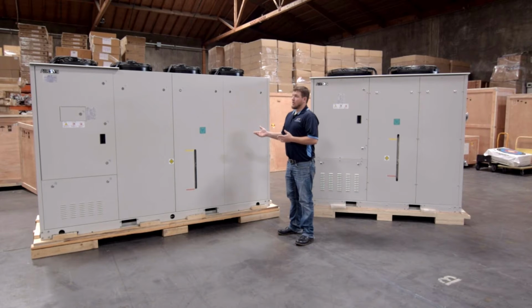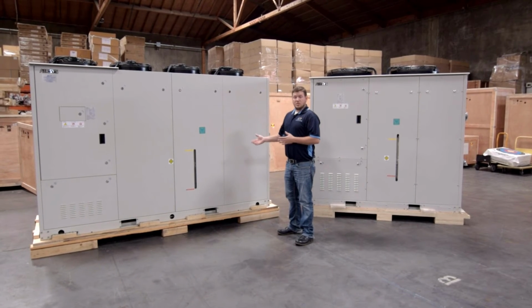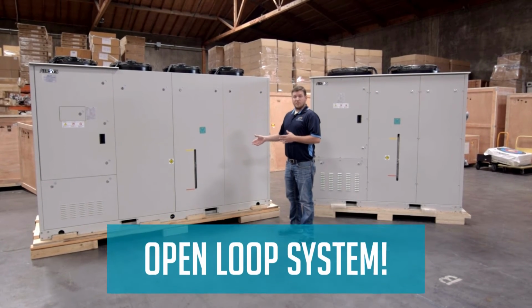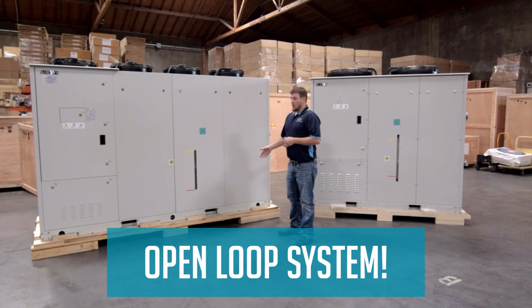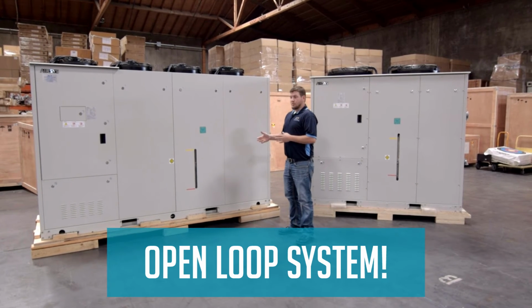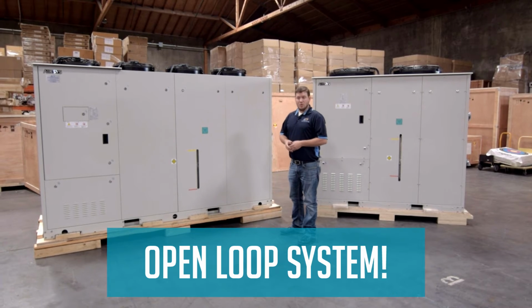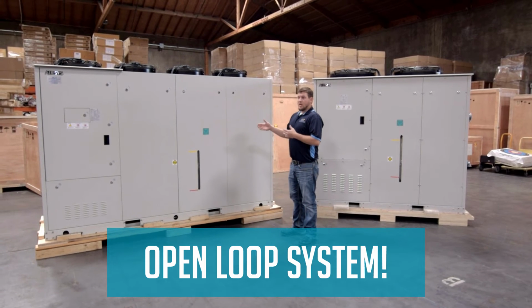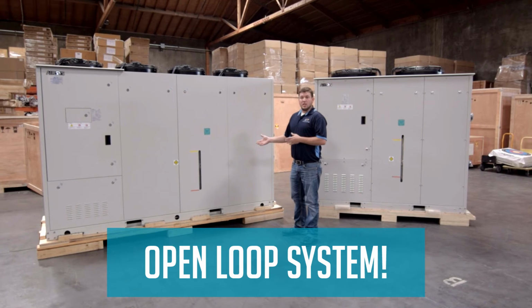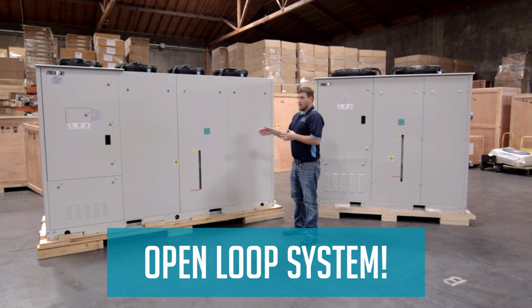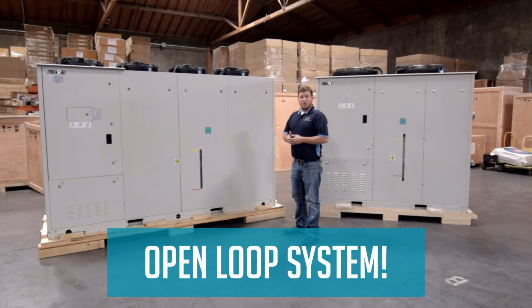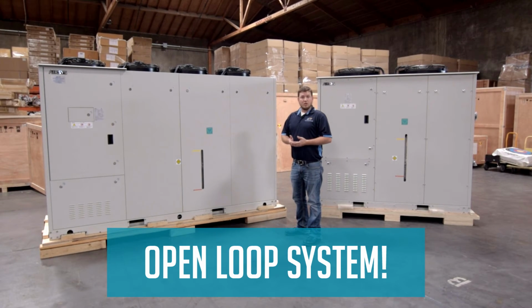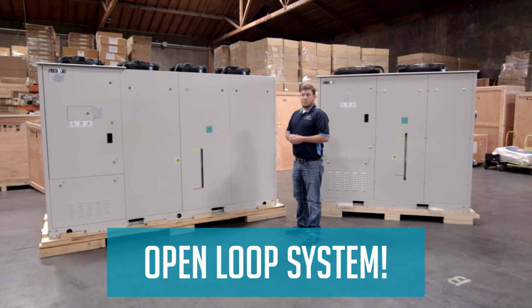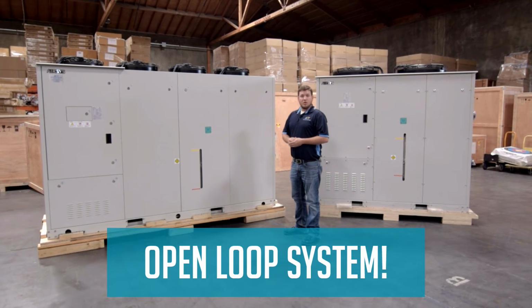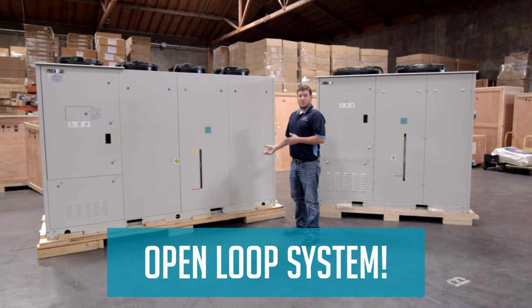There's also another great benefit to this system. Airsys chillers use an open loop design for the glycol system. A great benefit to an open loop is the reduced risk of failures. If, for instance, we have a small leak inside your building, our chillers are able to monitor the glycol levels and can determine if there's a leak. We can potentially get a technician to your site, repair the leak before the chiller ever faults.